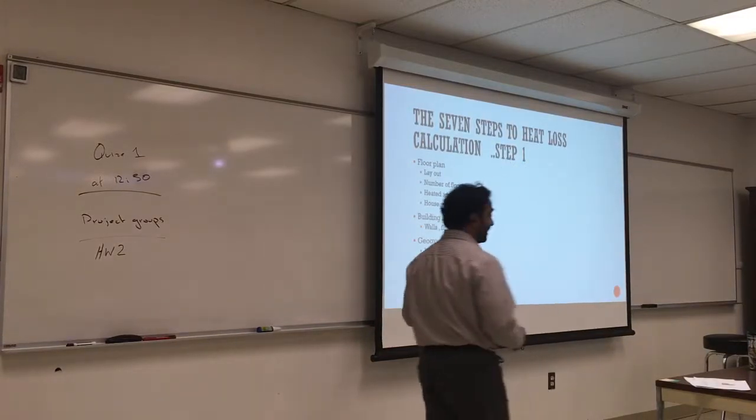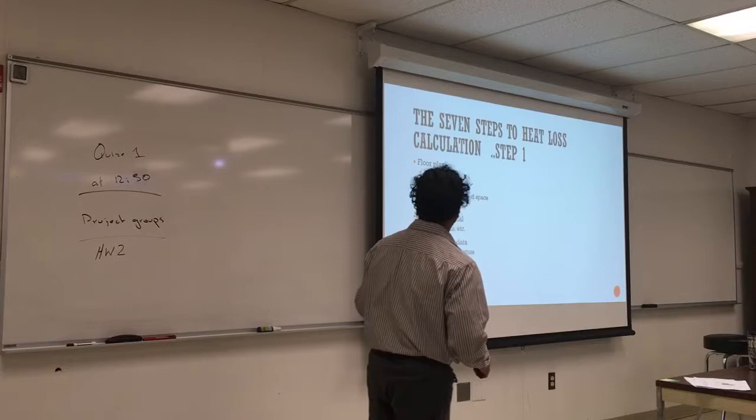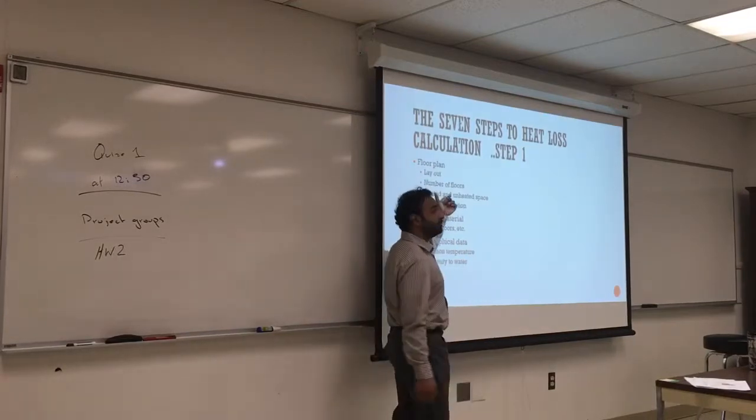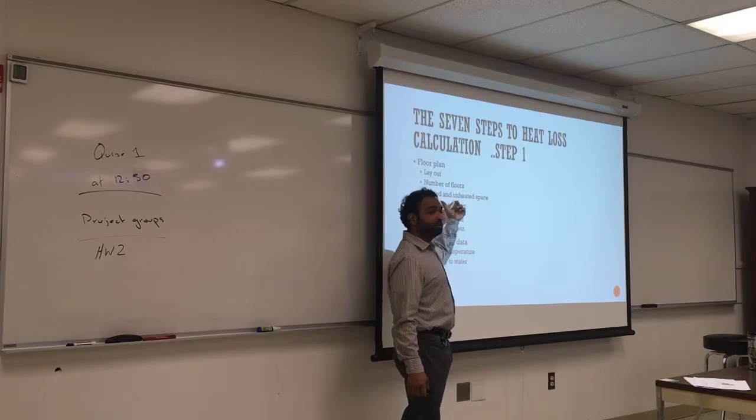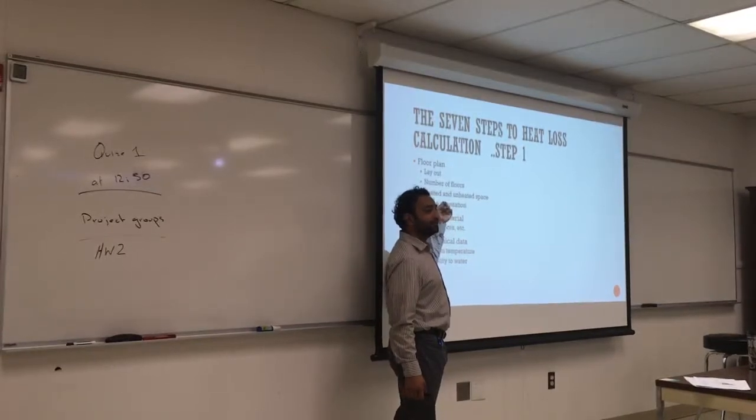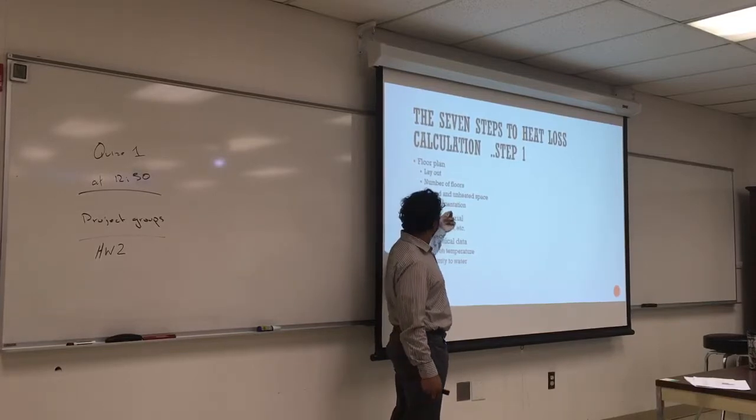So step one again, everybody has a floor plan. Get the floor plan, it has a layout, has a number of floors. Make sure you have this information. We want to decide which is the heated and unheated space, because there is no reason to include unheated space that will increase your heating load.